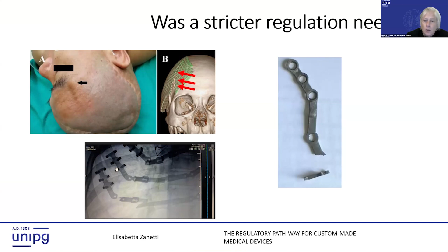If we look at the workflow for medical device certification, we can see that the difference between custom-made devices and standard ones mainly takes place at step 6 of this procedure, where we find product verification and validation. The reason is that custom-made devices are exempt from clinical evaluation. And it could not be different, because this would not be a viable option for devices which are actually made one by one.